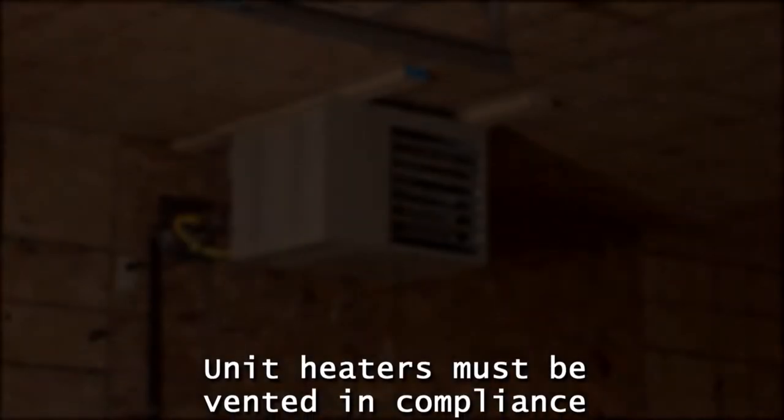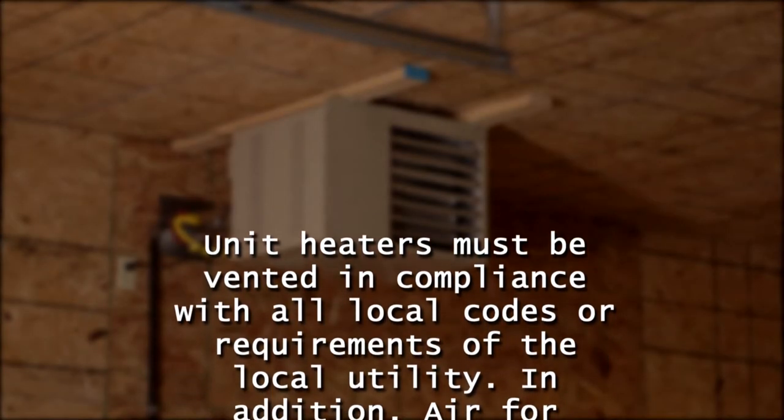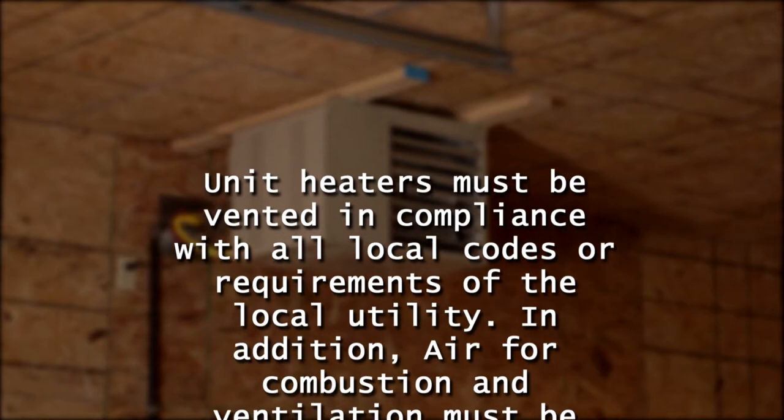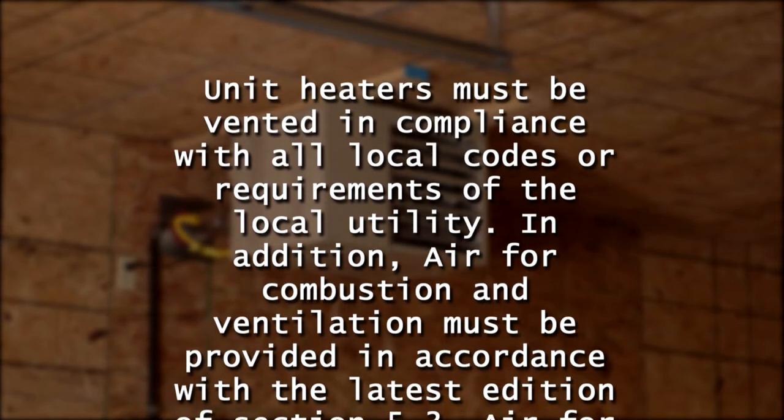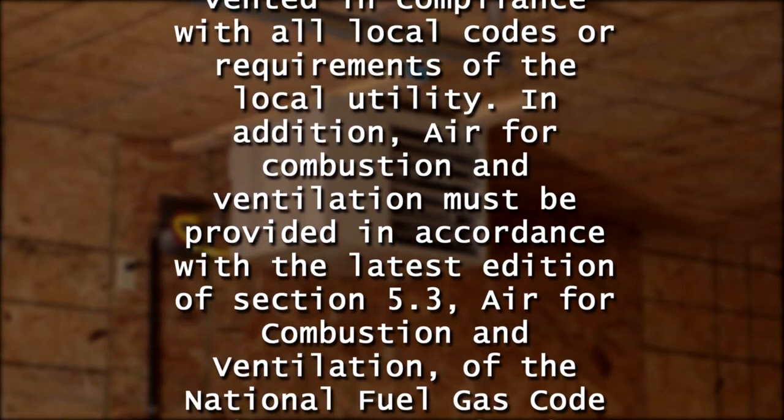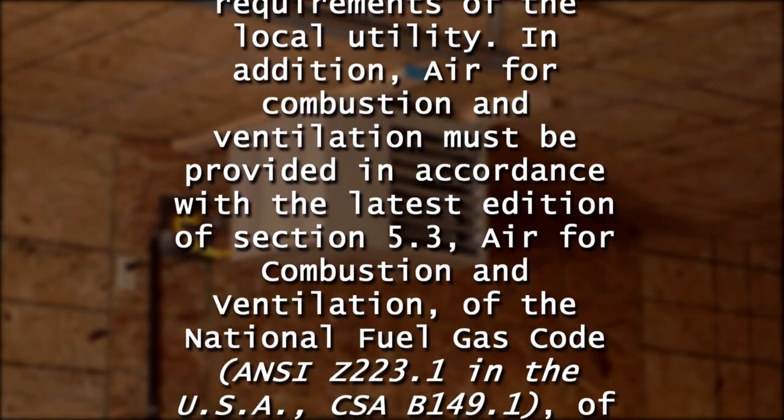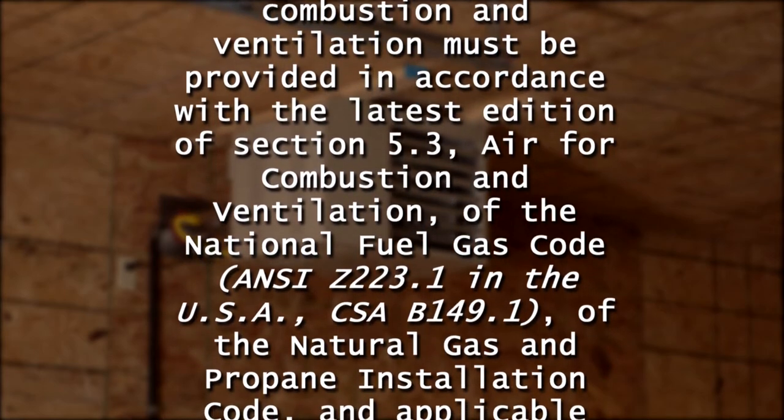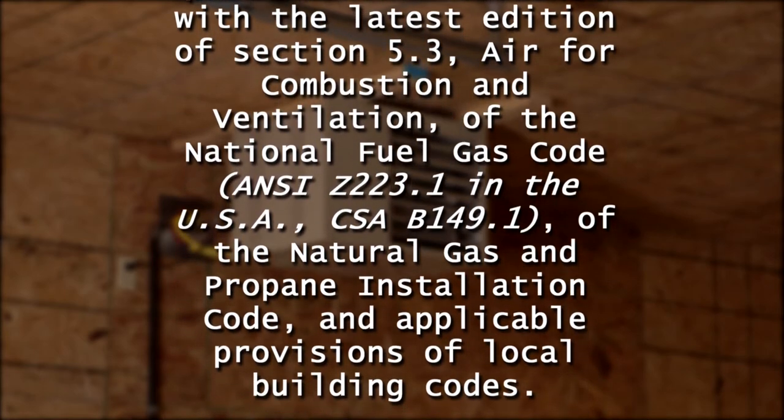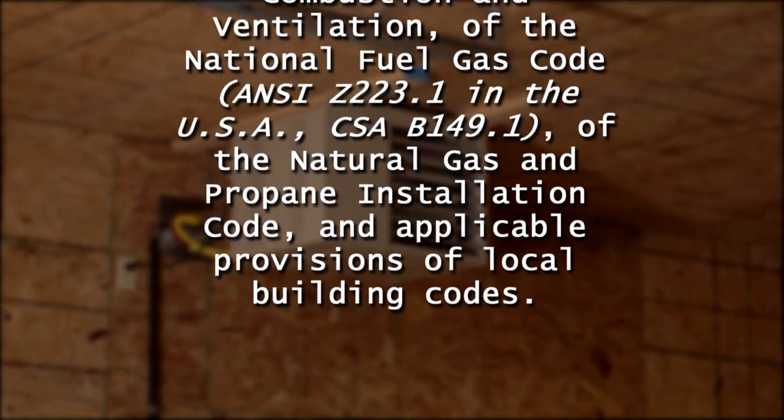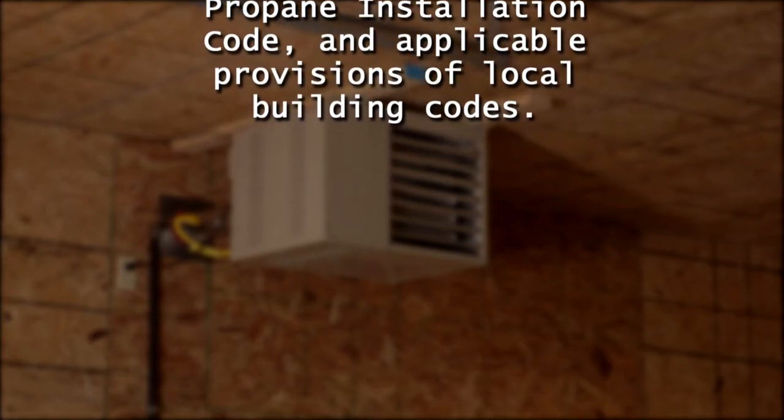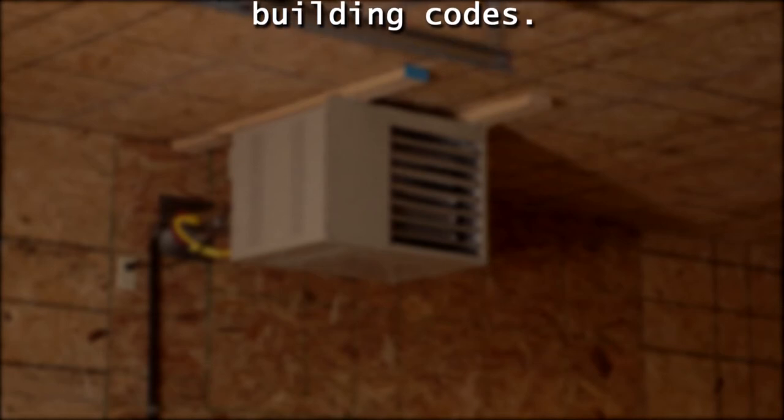Unit heaters must be vented in compliance with all local codes or requirements of the local utility. Air for combustion and ventilation must be provided in accordance with the latest edition of Section 5.3, Air for Combustion and Ventilation, of the National Fuel Gas Code, that's ANSI Z223.1 in the U.S. In Canada, CSA B149.1, of the Natural Gas and Propane Installation Code and applicable provisions of local building codes.